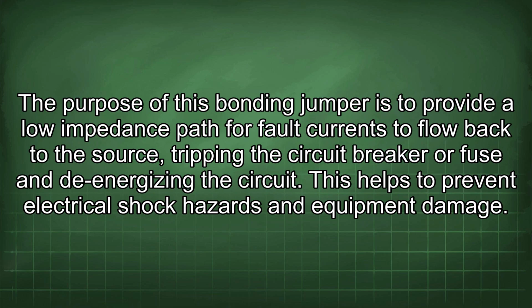The purpose of this bonding jumper is to provide a low impedance path for fault currents to flow back to the source, tripping the circuit breaker or fuse and de-energizing the circuit. This helps to prevent electrical shock hazards and equipment damage.